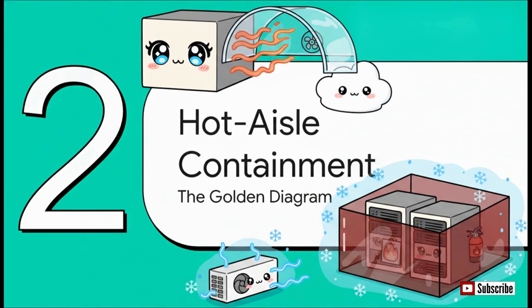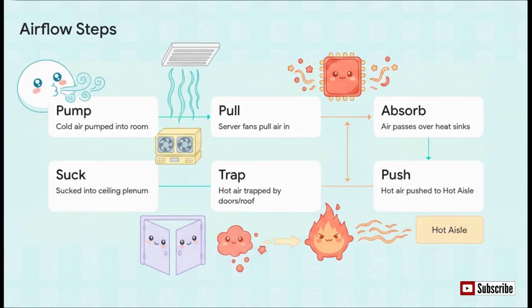Section 2: hot aisle containment. This is essentially the golden diagram of data center cooling. Let's trace the exact fluid dynamics of how this containment system works, because it's brilliant. By physically walling off the hot exhaust, we let the rest of the massive data center room act as a giant, safe reservoir of cold air.